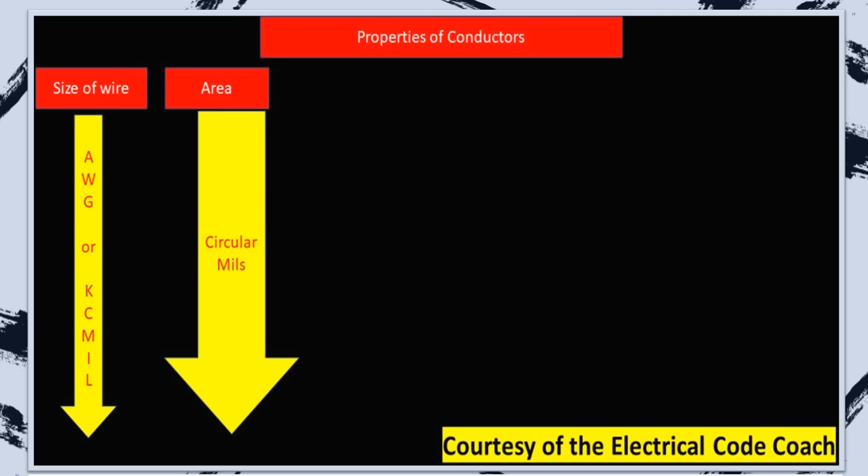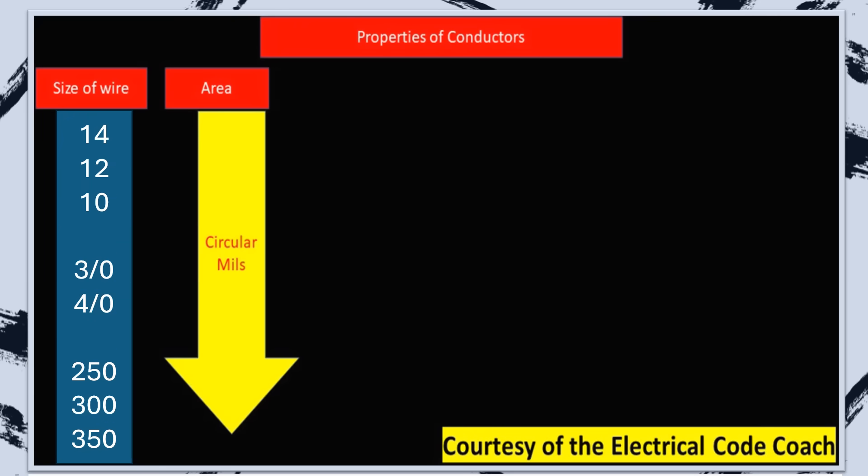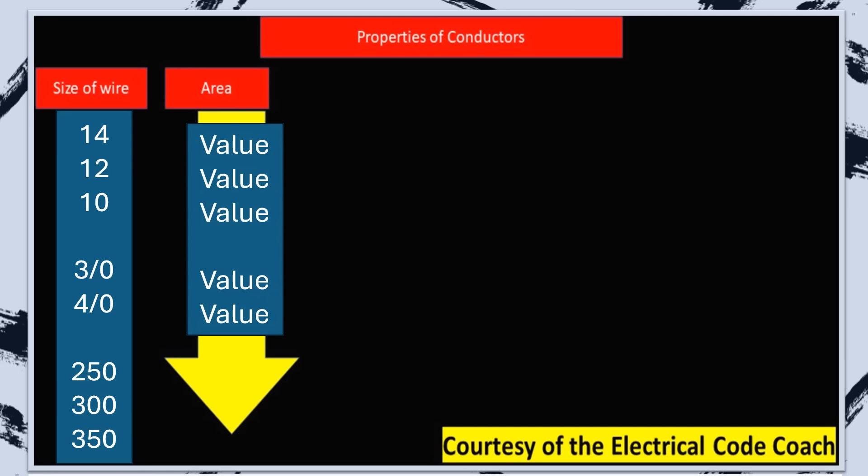On the left hand side, we're going to find our size of wire. You'll notice all of your familiar friends: 14, 12, 10. Then it goes down into larger numbers like 3/0 and 4/0. Then it goes into the kcmils. That's where we get those circular mils from: 250, 300, 350. In the next column over, we need to be sure to be in the area section, because that's where we're going to get our circular mils value. Each wire has a circular mils value.